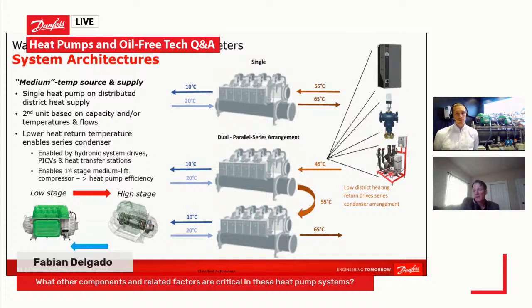Along with that, efficient heat transfer stations, as opposed to heat transfer stations in that district energy system that were applied 20 years ago. Same thing again on the cooling side: those rooftop units or air handling units or fan coil units, I think is a better analogy, that were applied 20 or 30 years ago aren't very efficient at heat transfer anymore. Same thing with the district energy system and the heat transfer station. So that heat exchanger, along with the pressure-independent control valves, is what enables that lower district heating return temperature. In turn, that enables a more efficient series counterflow or parallel series counterflow heat pump based system. I hope that answered the question.